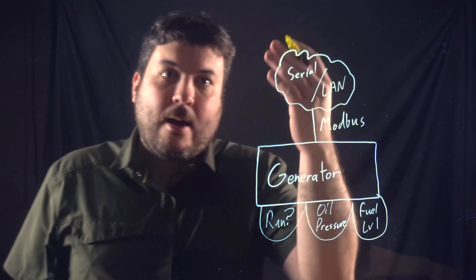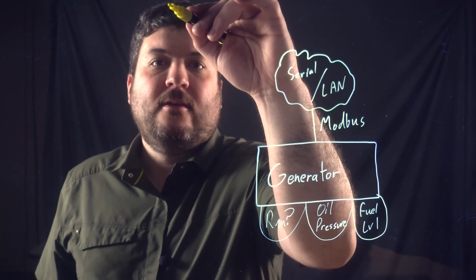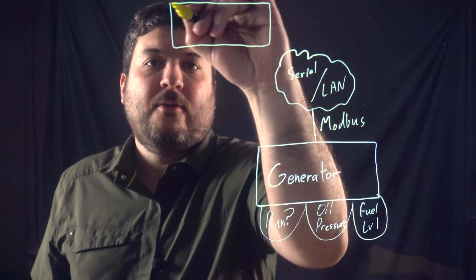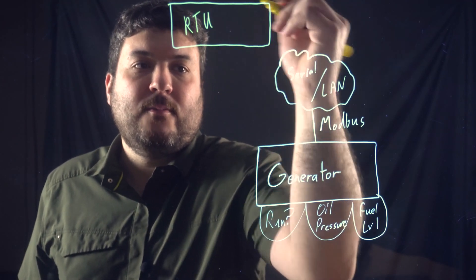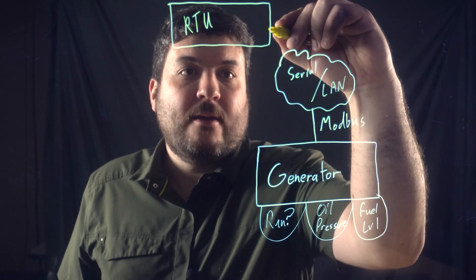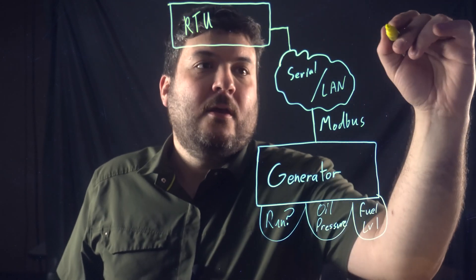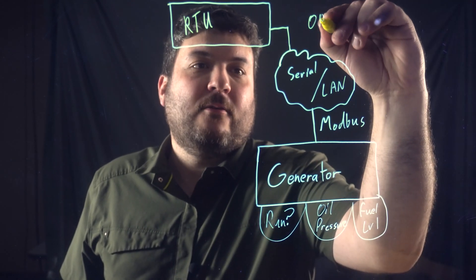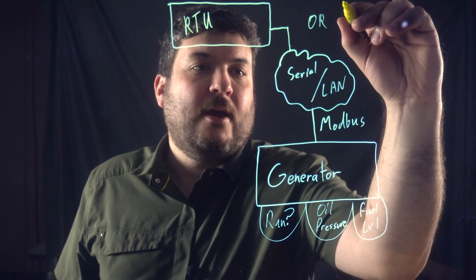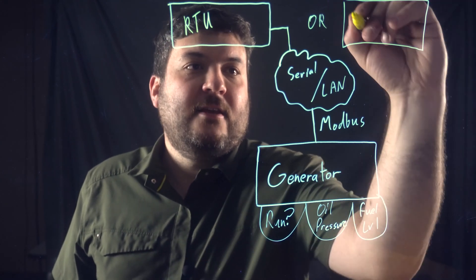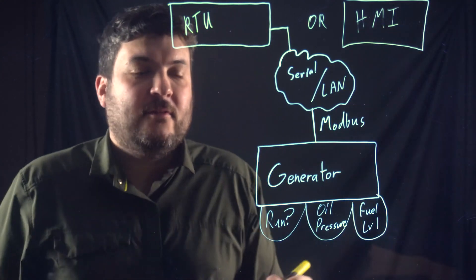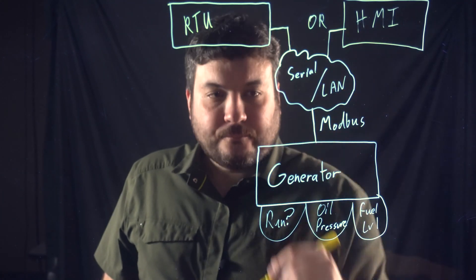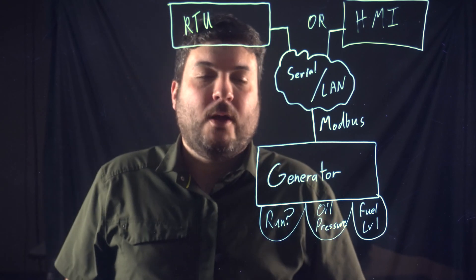And then you're going to have some top-level device. And this is, well, there's a couple things it could be. It could be an RTU, like a DPS NetGuardian is one example. And that would commonly be connected via serial. You could also, and I guess I'll write an OR here, you can also have just any SCADA HMI, and that's usually going to happen over LAN if it's talking directly. That one could be polling the generator as well.